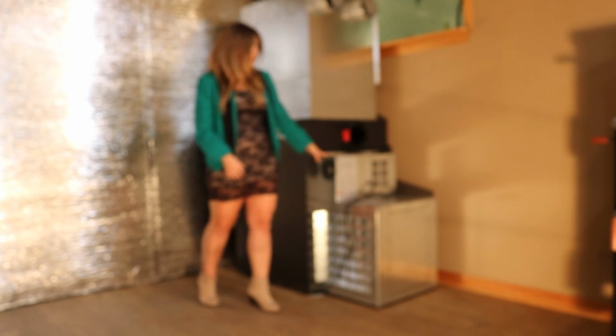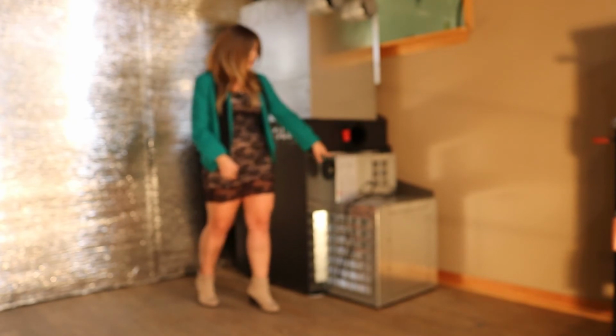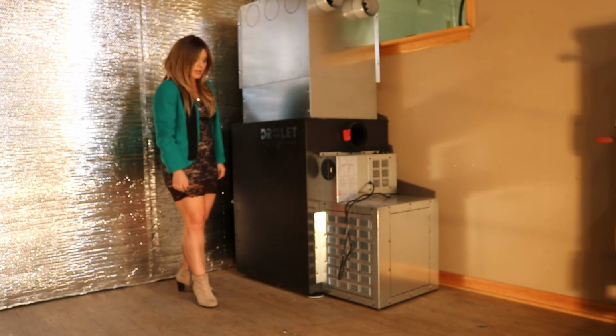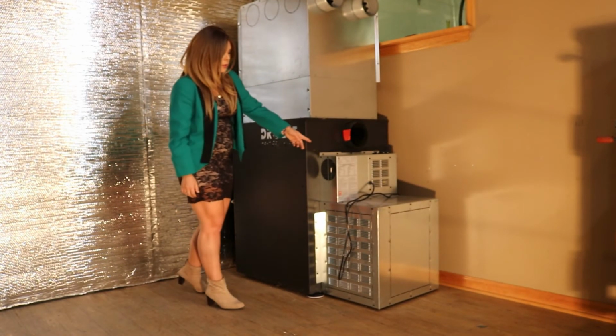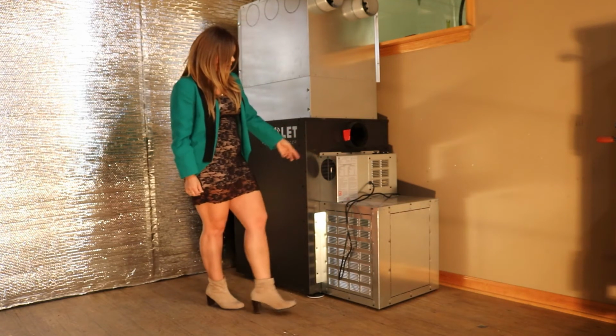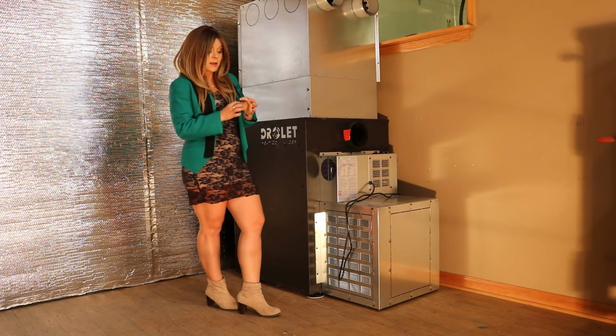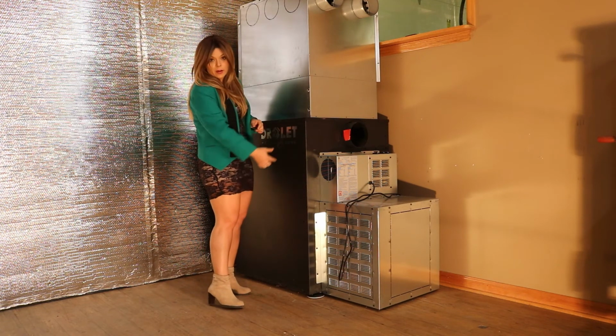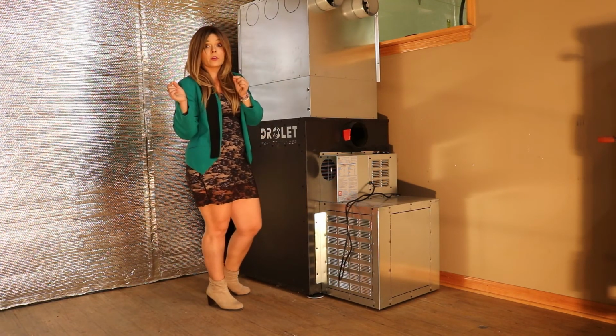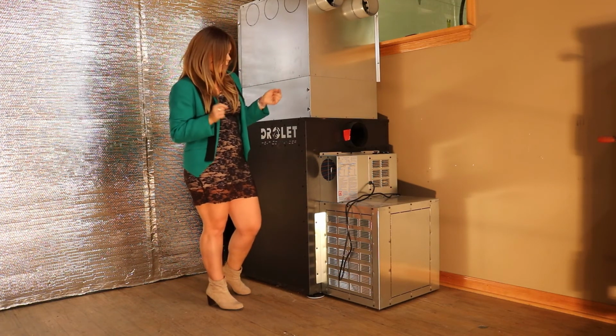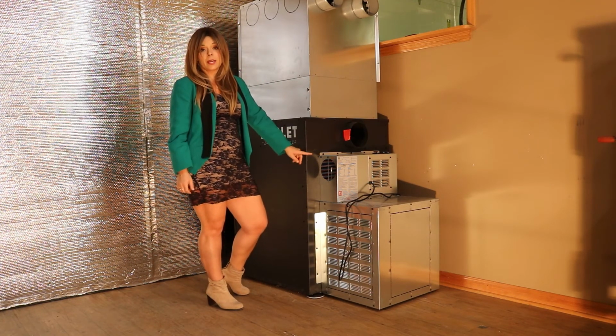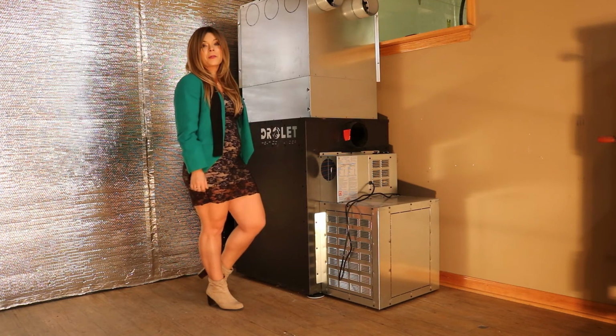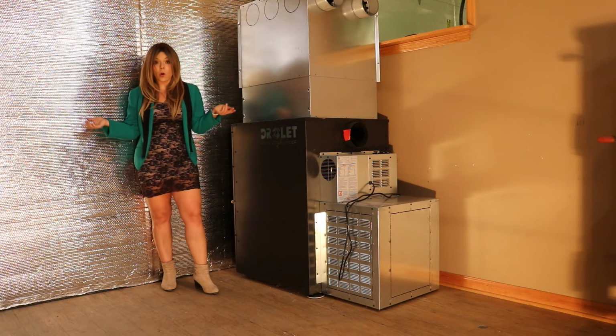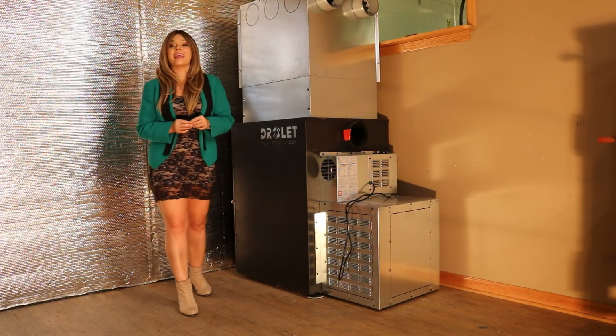Now again, if you had a system that stopped working, you could take apart in here, and on the diagram it is called the limit switch. I believe it's item 92 on page 79 of the manual, 92 or 94, and it's called the limit switch. Now this limit switch will also activate the damper air hole inside the firebox. So if you notice maybe one of your damper holes, air holes, is not opening up into the firebox, that could also potentially be a limit switch issue. So I hope that you guys found this technical overview helpful on the Drolet Heat Commander.